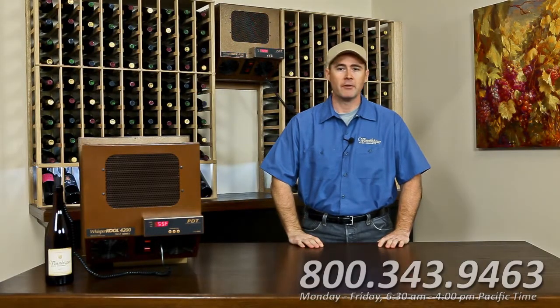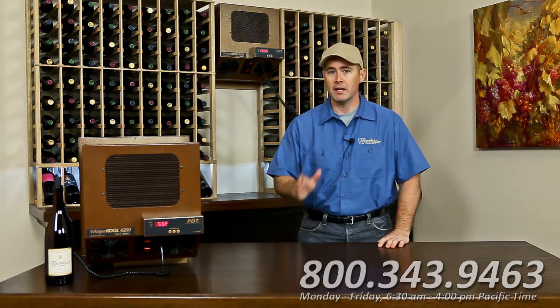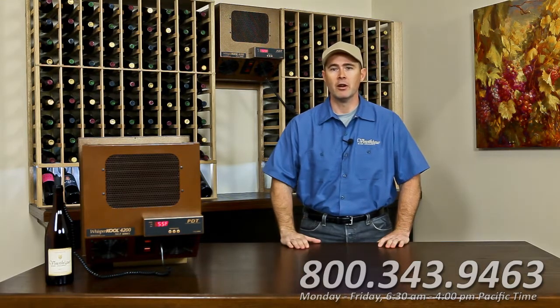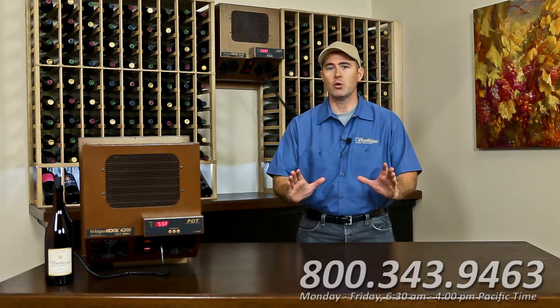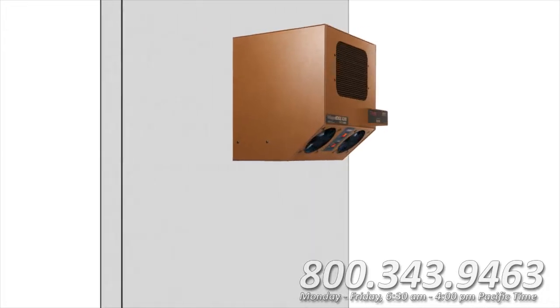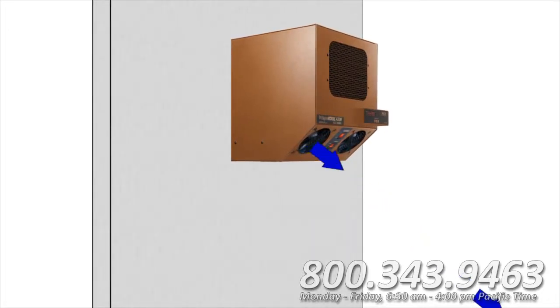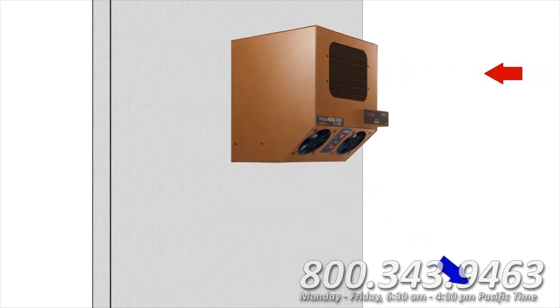What if your unit is running, but it's not cooling the cellar? If your unit is not cooling to 55 degrees, and you've confirmed this with a separate thermometer, there are a few things you need to do. But first, let's take a look at the position of the cooling unit in the cellar. If the cooling unit is not mounted high on the wall near the ceiling, it will not be able to circulate the rising hot air, and you won't get proper performance from the unit.